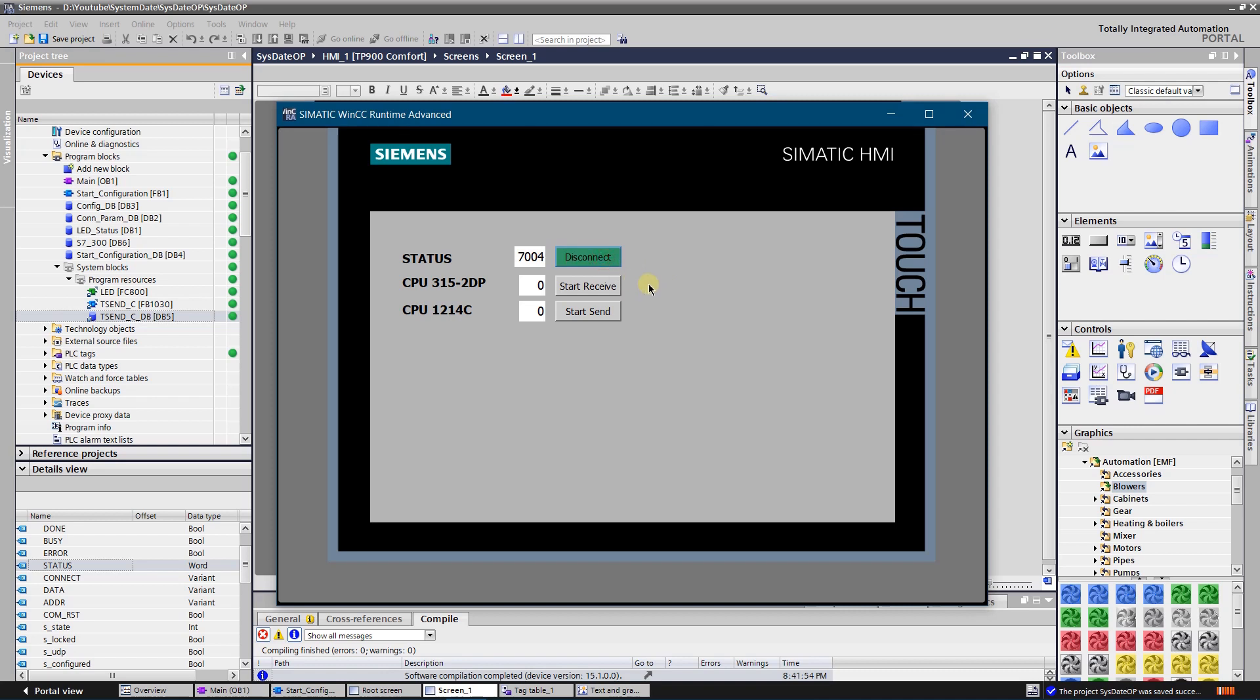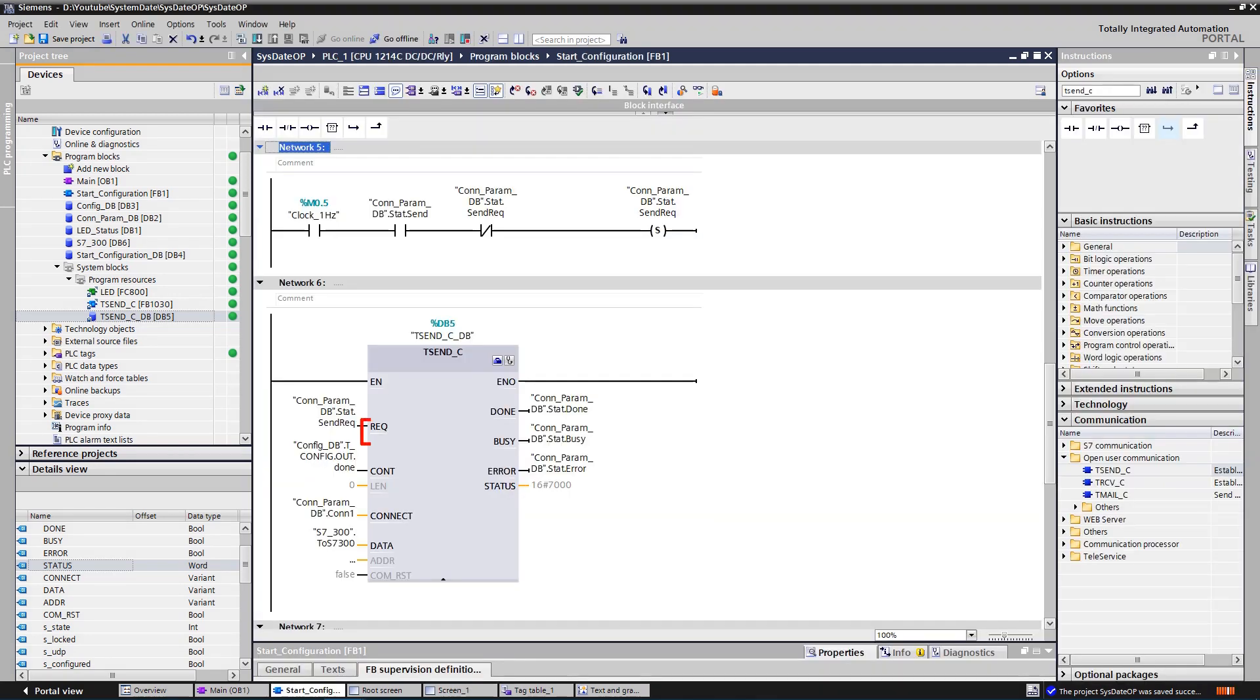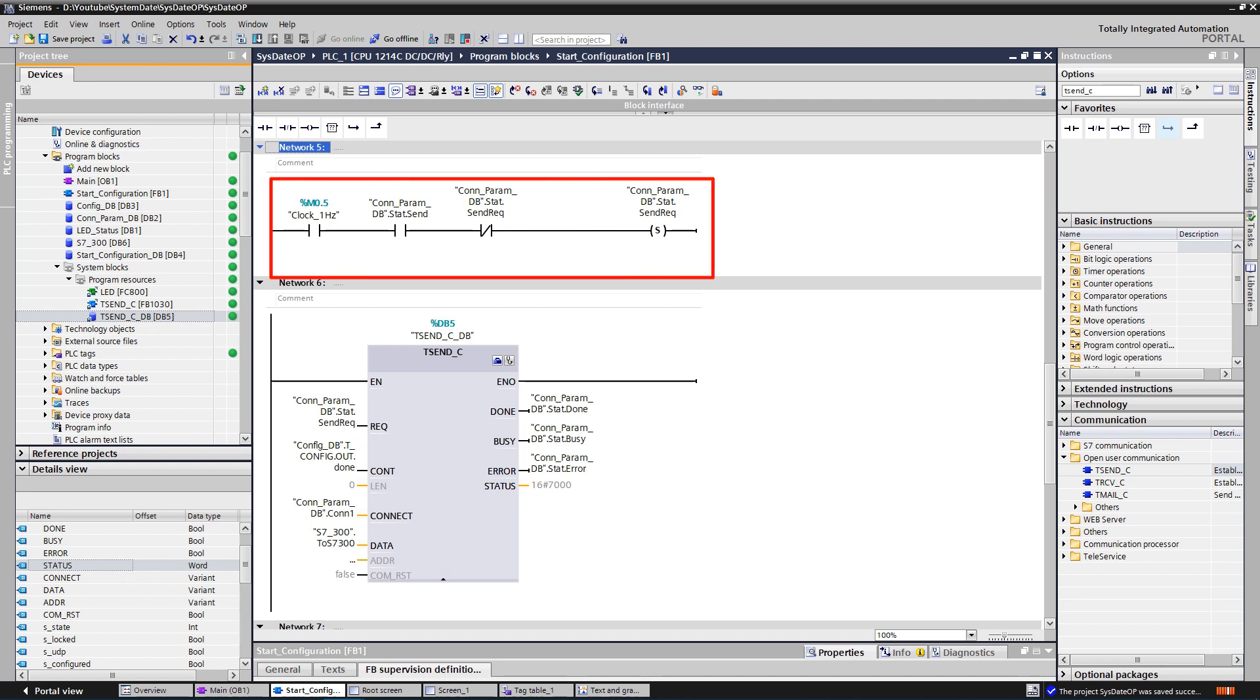In this example I am going to send one byte to the remote S7-300 series station. At first I need to activate the receive on the S7-300 station side. To activate the send job on S7-1200 side, you need to set input REQ of the T-Send-C. I do send one byte on the regular one hertz interval.